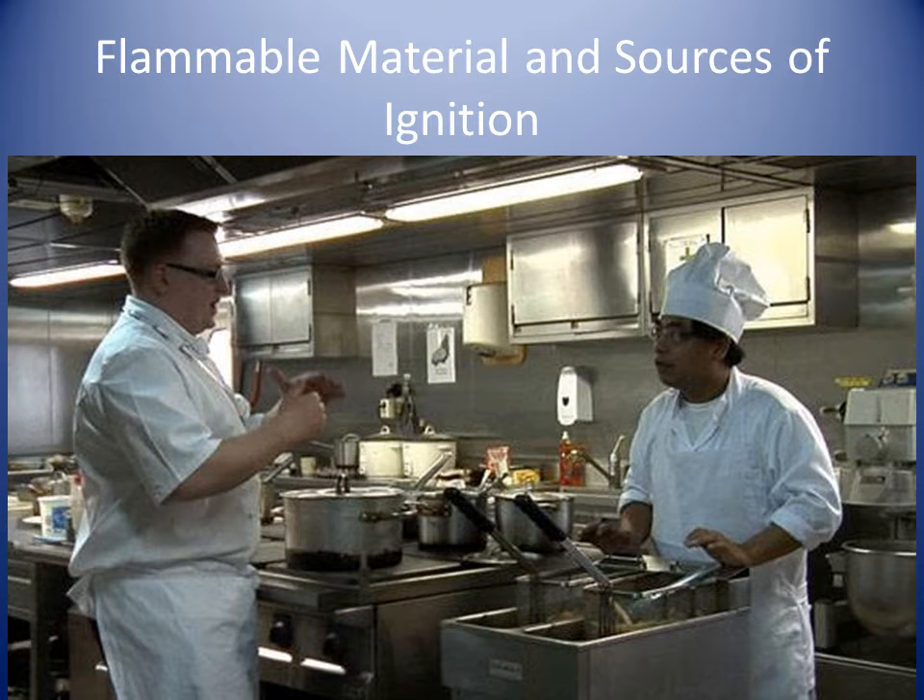In a small cooking area common with the accommodation, fire protection is dependent on the fire hazard presented. High fire hazard appliances, e.g. deep fat fryers, are not permitted unless the compartment is fitted with fixed fire extinguishing equipment. Suitable fire retardant barriers shall be built around hot appliances adjacent to combustible material.